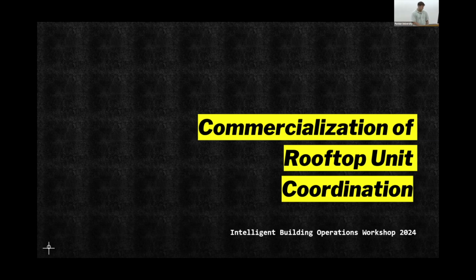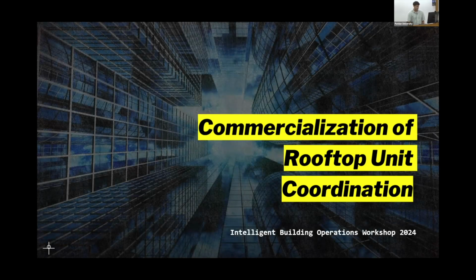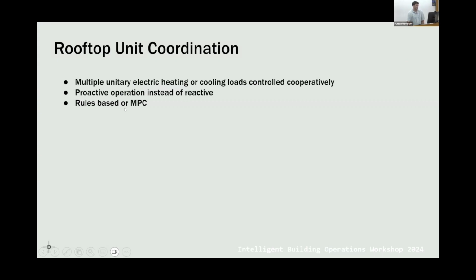The objective was to use the multiple unitary electric cooling loads to distribute them by anticipating what the cooling loads will be ahead of time. And by cooperatively controlling the building using a supervisory control algorithm, reduce the overall demand of the building. You can have rules-based unit coordination, or you can have model predictive unit coordination. The application we chose was to take the model predictive route.